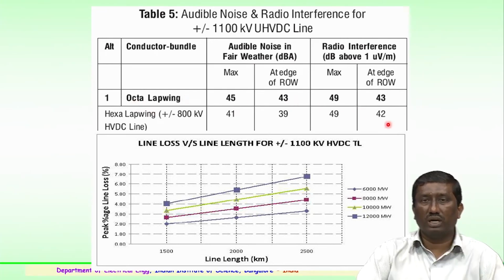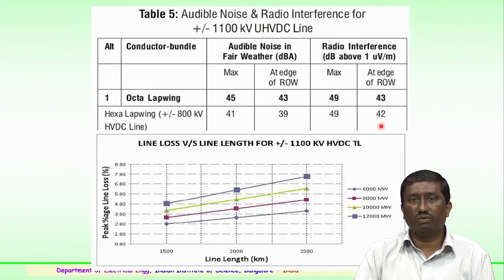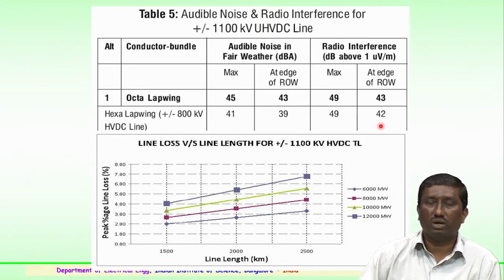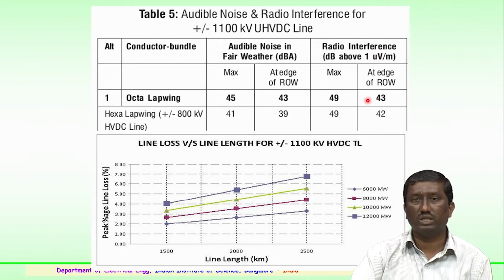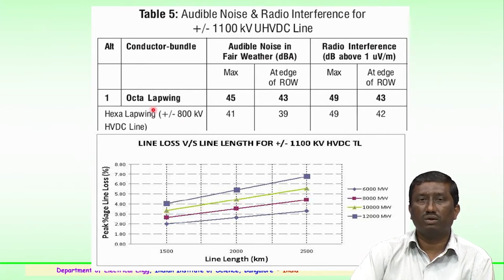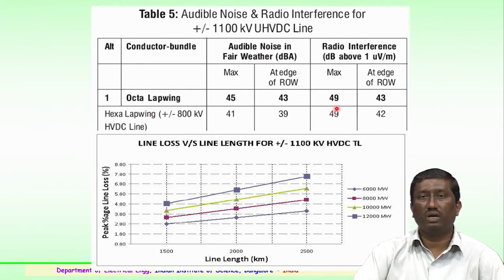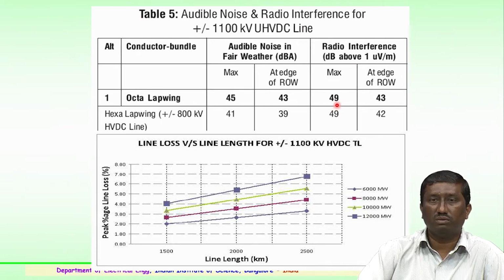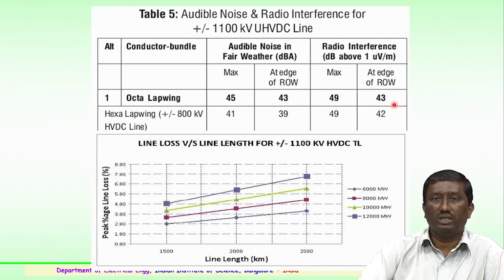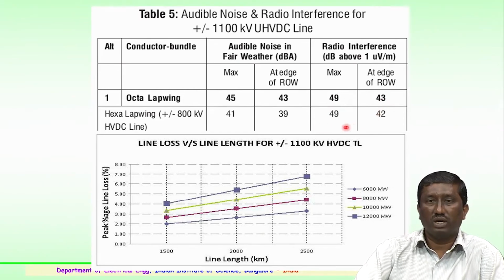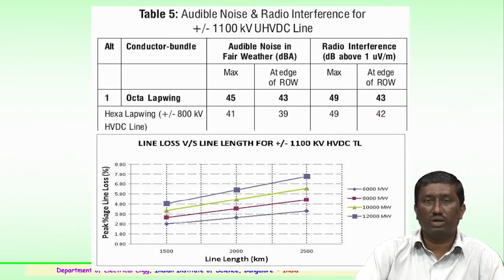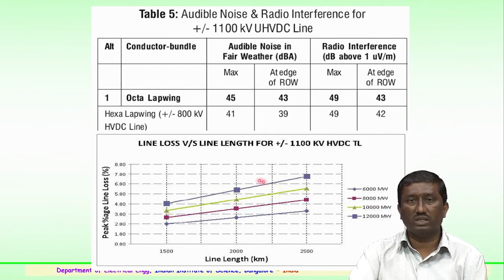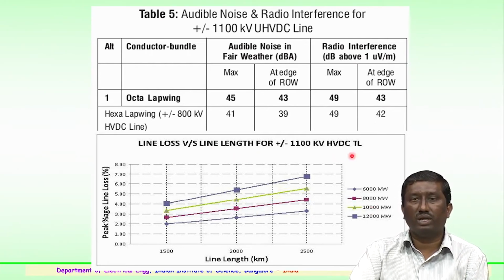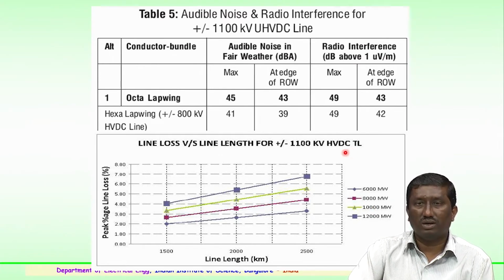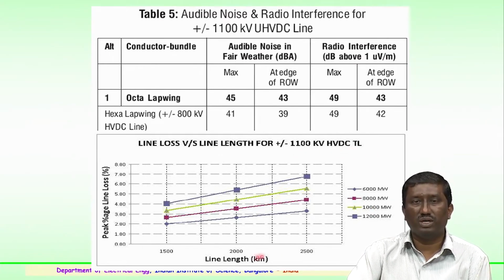So, this will again adhere to the international norms of not crossing 1000 microvolts or 60 decibels for radio interference. Here you can see that going in for octa lapwing conductor, a maximum of less than 50 decibels and 43 at the edge is being obtained, whereas for 800 kV presently it is 49 and 42 respectively. So, the line losses versus the line length for 1100 kV ultra high voltage transmission, as estimated, is shown here.